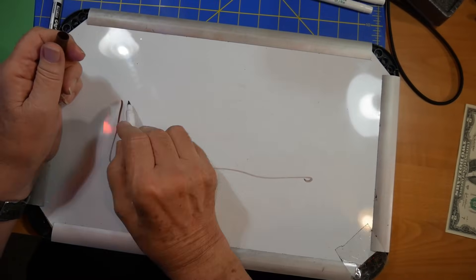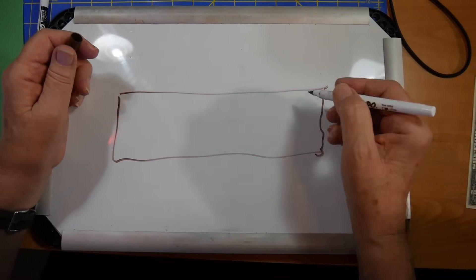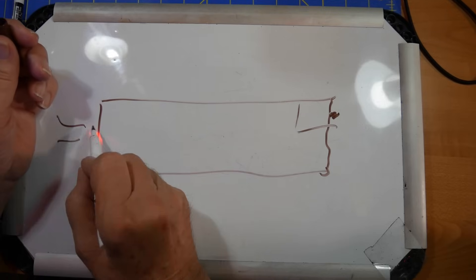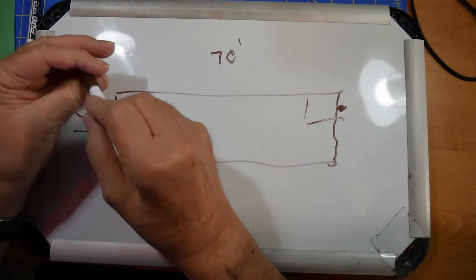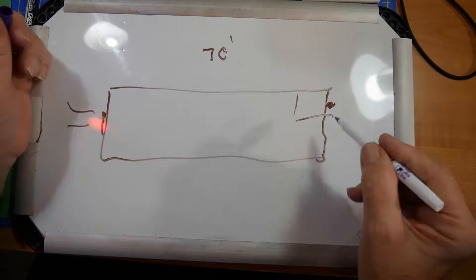Is there really no practical range for bonding a separate grounding rod to the main house? Let's take a look at this on the whiteboard. This right here is the long rambler-style house — one story. He might have a bedroom here. This is his shack and he's got a ground rod right here. His electricity comes in over here where the meter is, the utility ground is here, and this would take 70 feet. Let's draw that in with this purple line here.